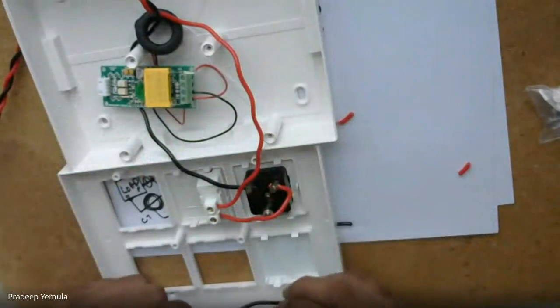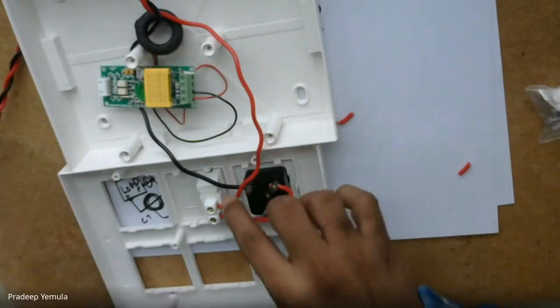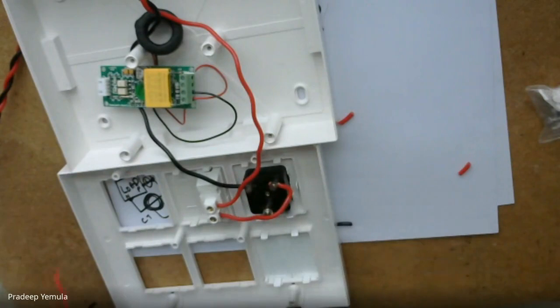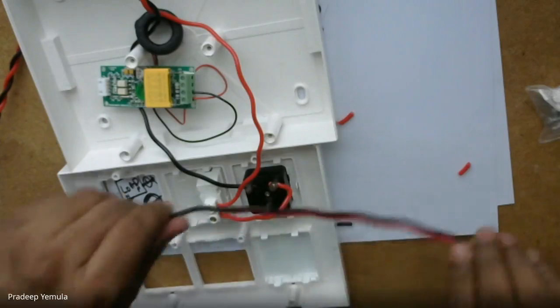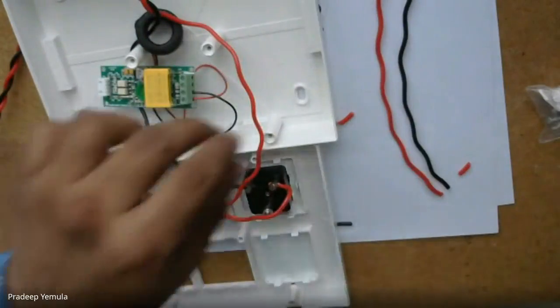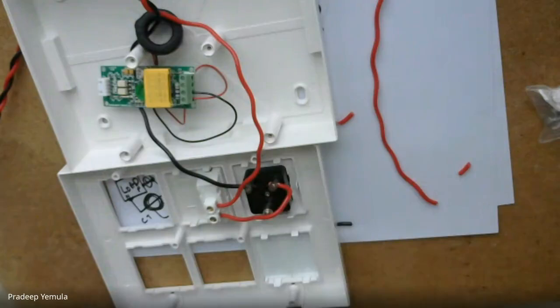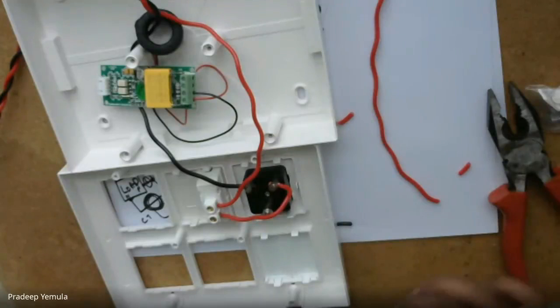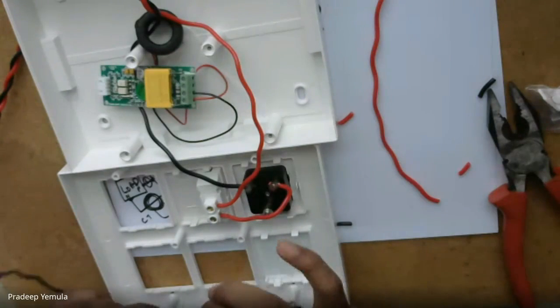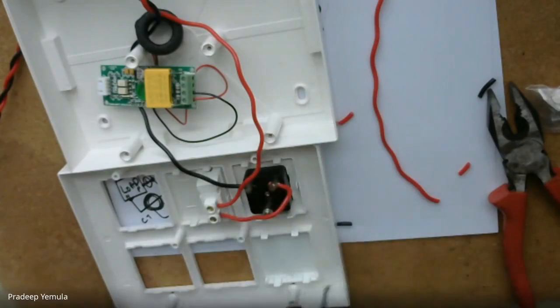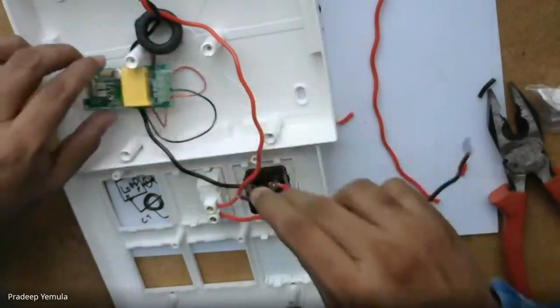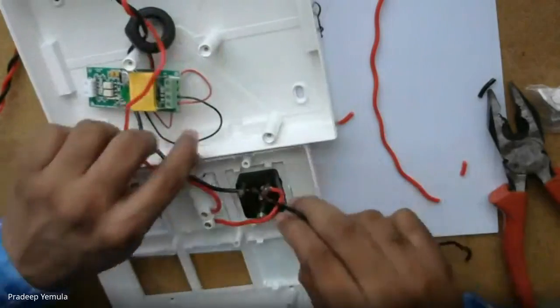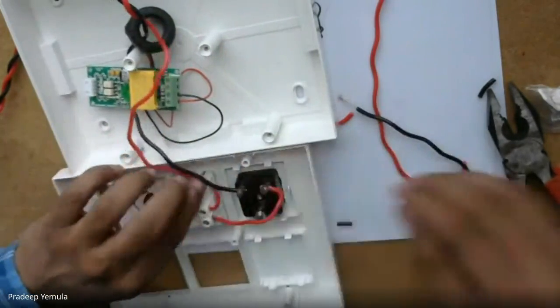So again, where will I get the phase and neutral? Should I go after the switch or before the switch? It is better to go before the switch, because even if the switch is off, the voltage will go to the device and it will make a measurement. And there it may measure zero current or something like that, which is okay. So now I'll incorporate this connection.